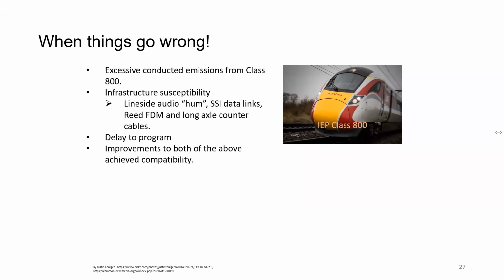Is there a mitigation measure if an EMC survey reveals problems after installation? It totally depends on the problem. If equipment is creating a problem - for example, a transformer creating excessive electromagnetic fields - the mitigation measure is to replace the transformer. If signaling equipment is creating noise above the limits, we can ask the supplier to retest or redesign the equipment, or bring a new one with lower electromagnetic emissions. There are many real instances after installation where electromagnetic levels were high and redesign was required.